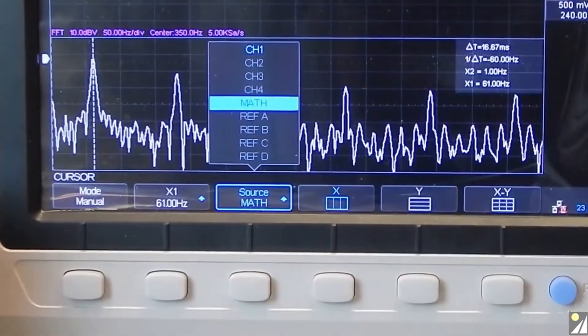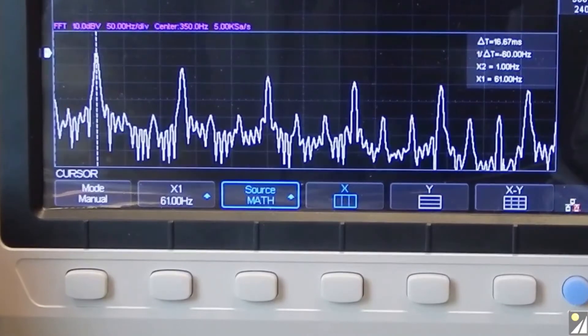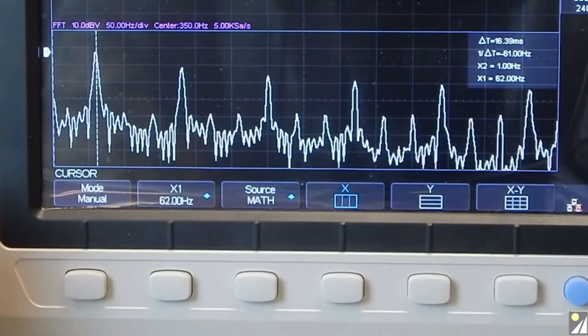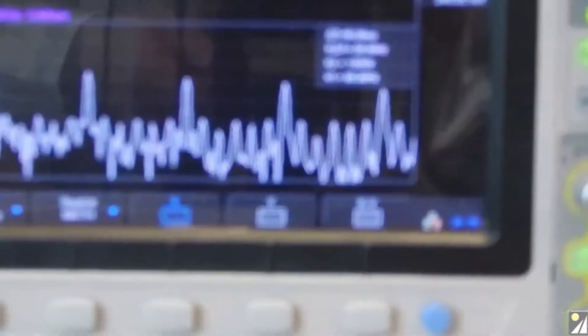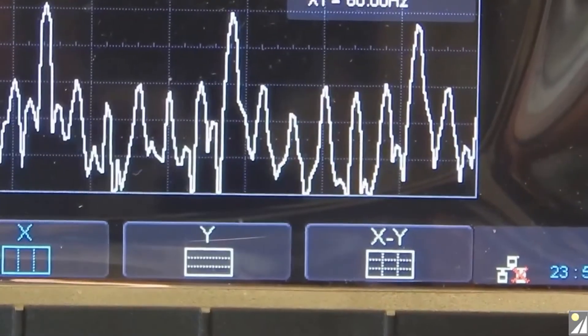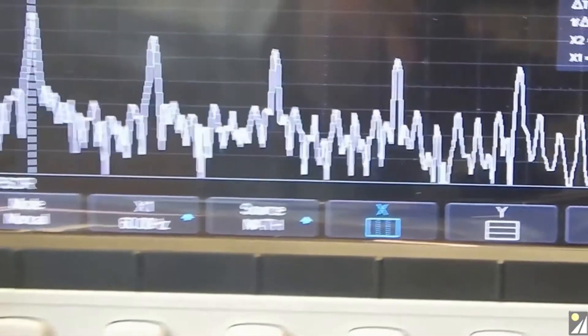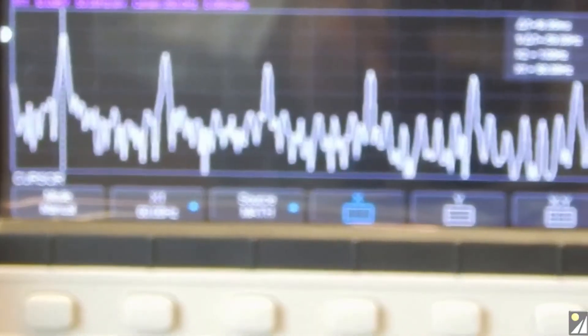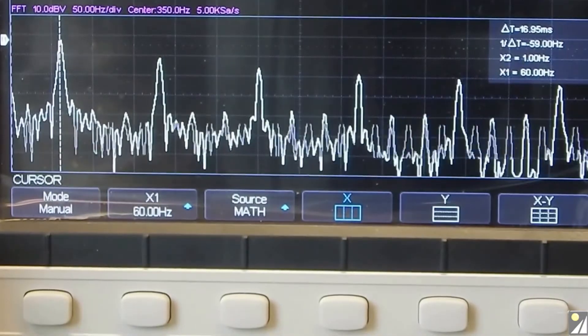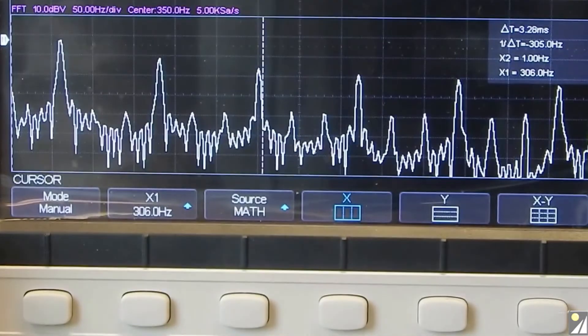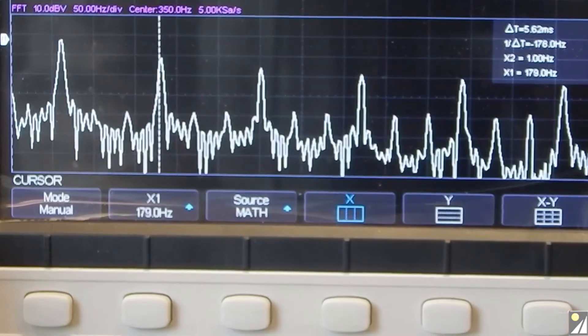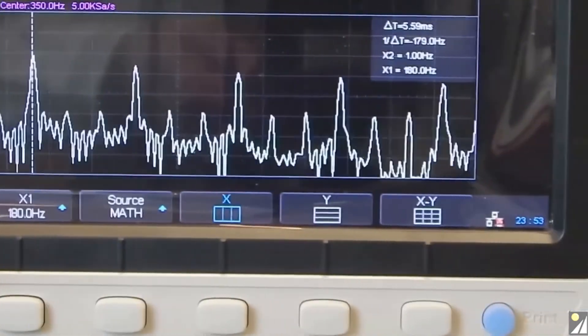Let's turn on the cursor just to verify that, and let's change this over to math. Okay, and sure enough, as we move the cursor we can see it's right smack on 60 hertz. And if we look at our first harmonic, that appears, that should be the third harmonic. You have 60 hertz, that would be 180, 180 hertz, which is what we get there on the screen. So it's operating just as we expected.